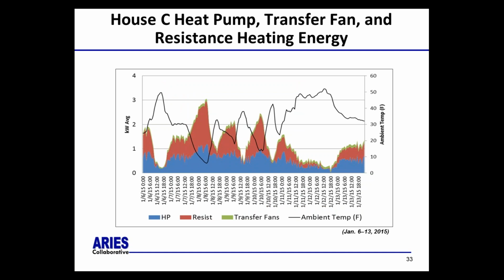So here's the breakdown for House C during that same heating period, showing the blue, which is the heat pump energy, the red is the backup resistance heaters, and the little green is the transfer fan energy. So that's the total space conditioning energy for the house. There is a lot of resistance heat energy. It's roughly half of the energy, but it's providing far less than half of the heat. But it's necessary to get the heat into those bedrooms.